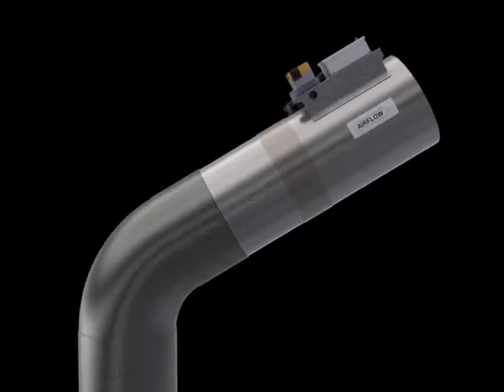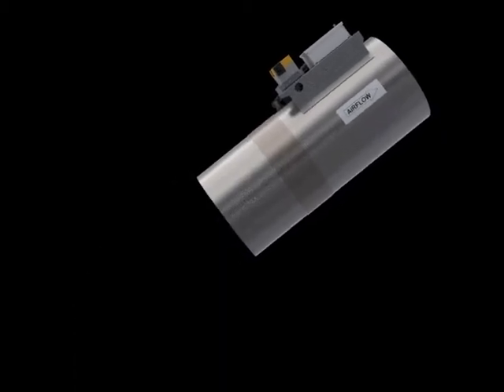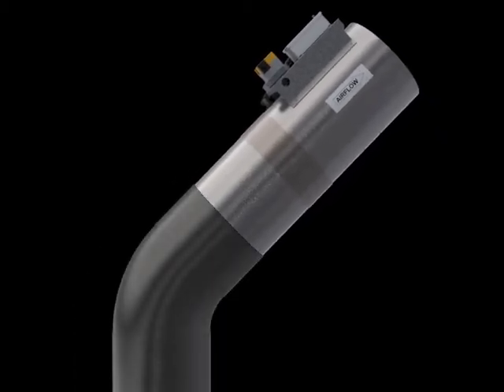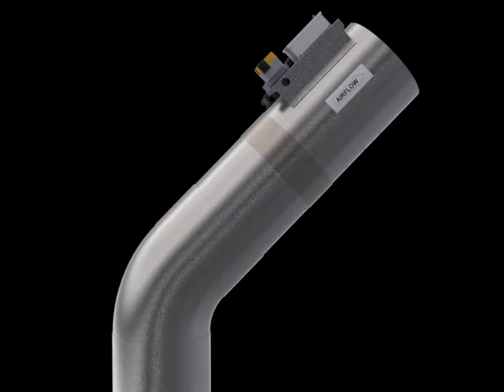Older valve designs, such as Venturi, must be ordered from the factory to be installed in either a vertical or horizontal plane, as they're factory calibrated for mechanical position of an internal spring cone arrangement.